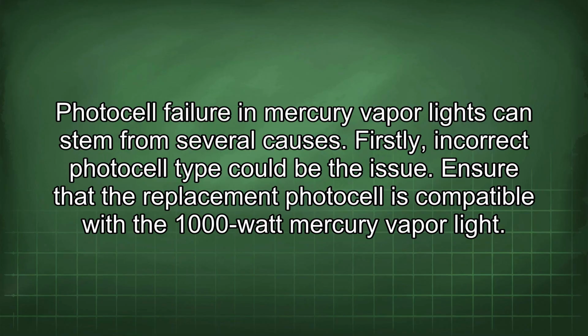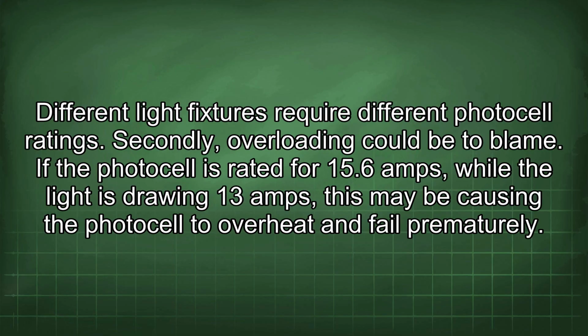Photocell failure in mercury vapor lights can stem from several causes. Firstly, incorrect photocell type could be the issue. Ensure that the replacement photocell is compatible with the 1000-watt mercury vapor light. Different light fixtures require different photocell ratings.